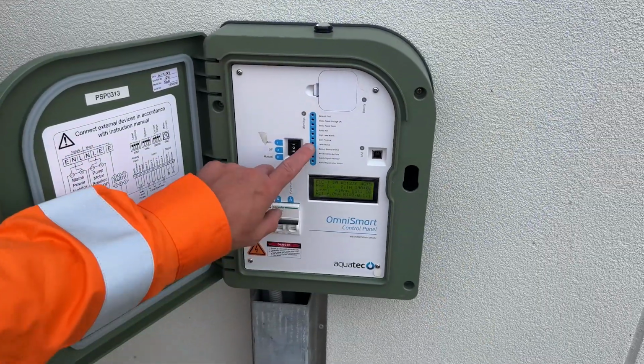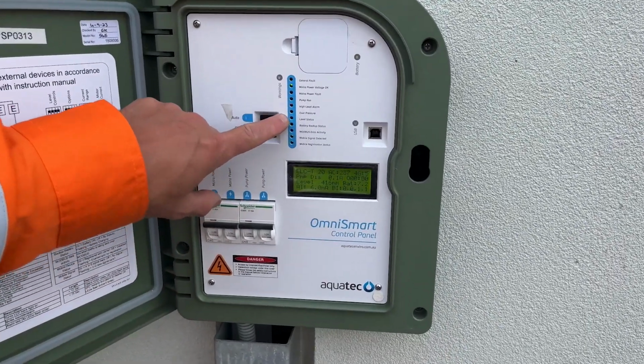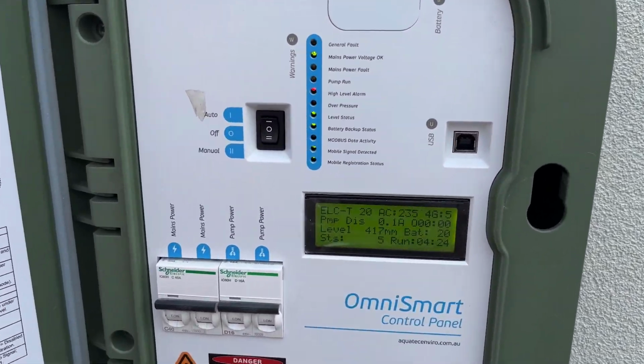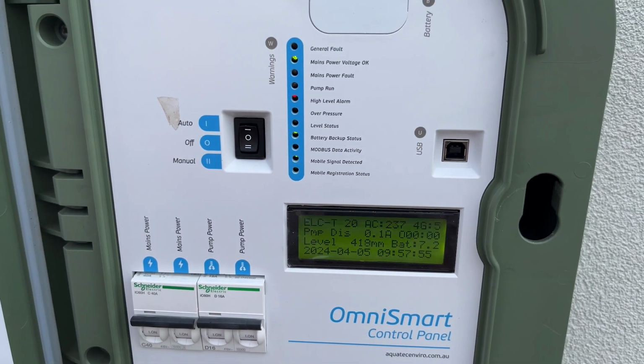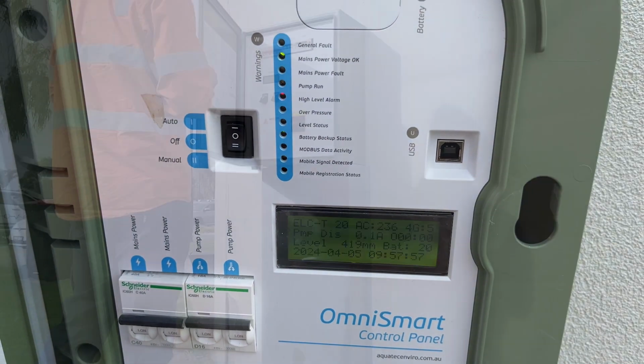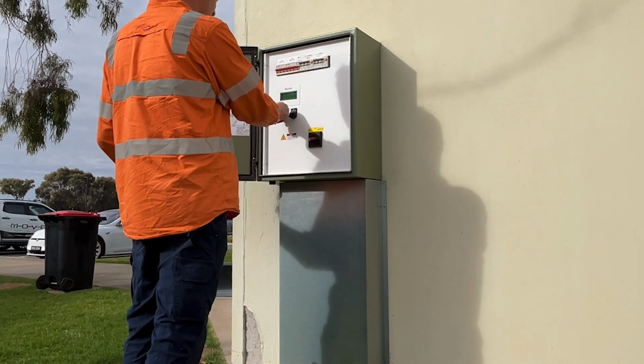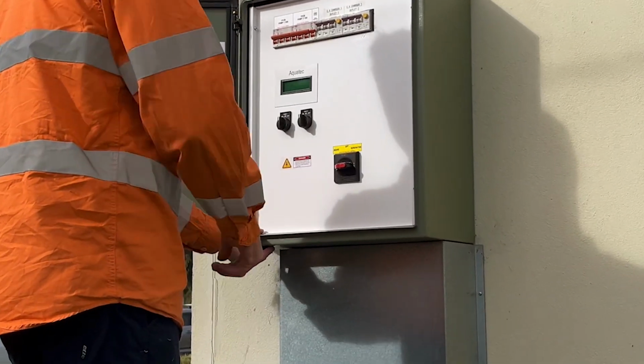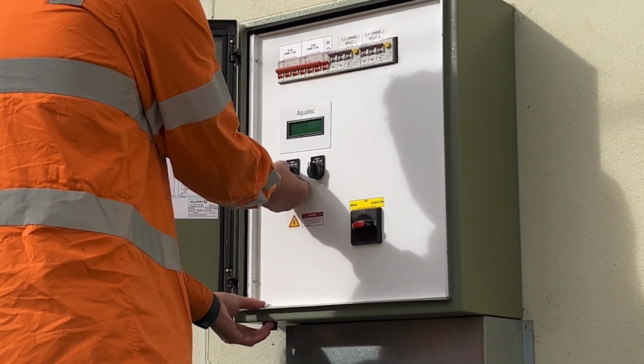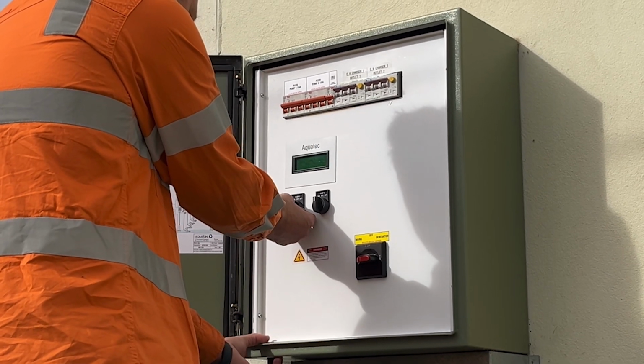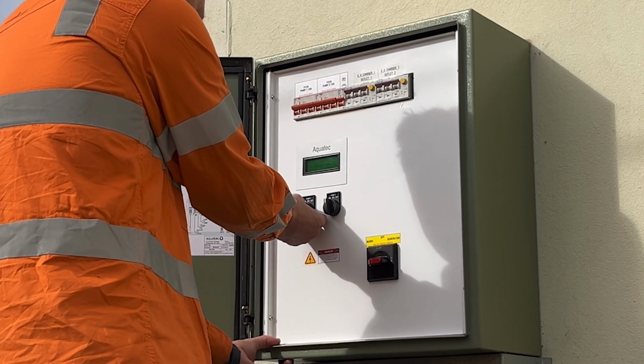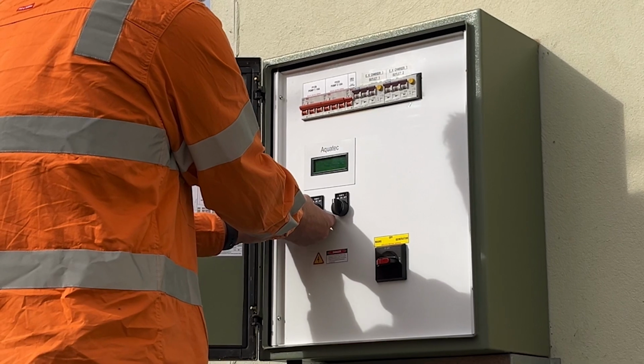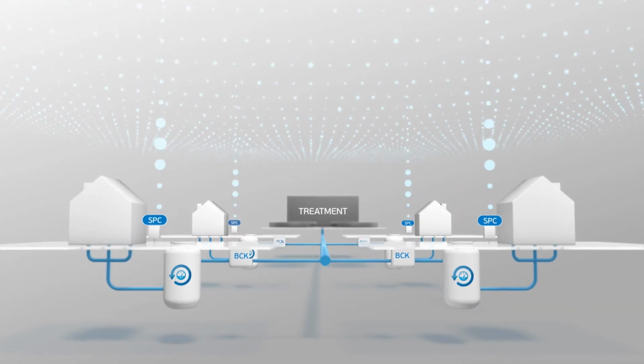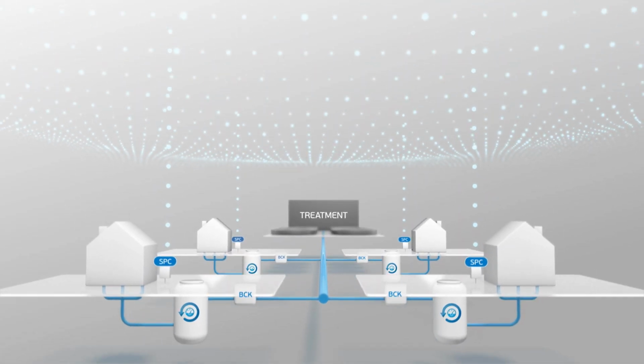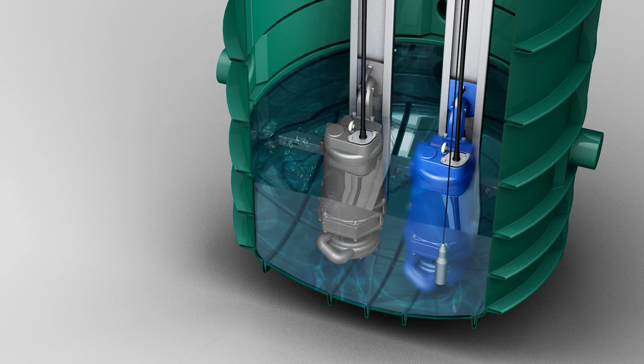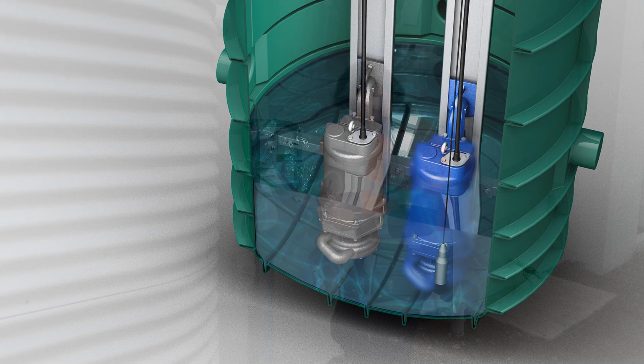Nearing the end of the pump cycle procedure, we're ultimately looking for the pump to turn off by itself. If your pump does not turn off and then you hear it drawing in air, something is not right. In any dual or multi-pump system, you should do this test at least twice to verify the pumps are alternating via the control panel. If the system is depowered for whatever reason because power is off in the street, water still runs. Your tank might get to a high level point. Power is then restored. There may be a slight delay between the pumps starting, but they will both run in the case of a dual pump system.